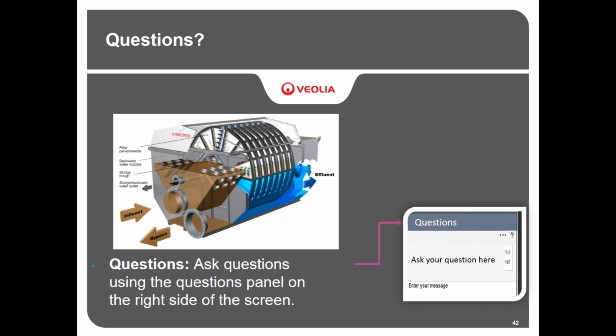Okay, looking at our list of questions here. Another question is related to the different types of pretreatment technologies for raw water. What would you select in terms of a traditional clarifier versus a high rate clarifier versus, say, these disc filters? So, the conventional clarification does work, but it tends to be much larger, which means it has larger cost for civil works and things like that. Where you start to see more and more benefit for the disc filter is when you get into extremely large flows, because they have a very high surface area. If you have large flow and low solids, where you don't have much to remove but it needs to be removed, that's the sweet spot for the disc filter.